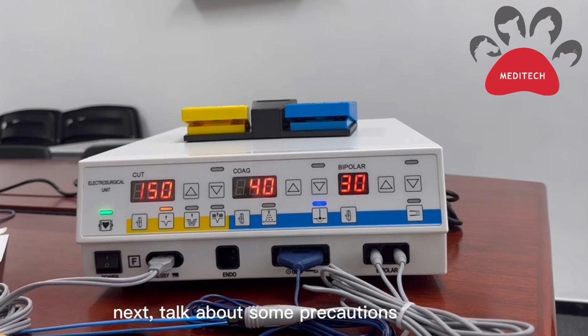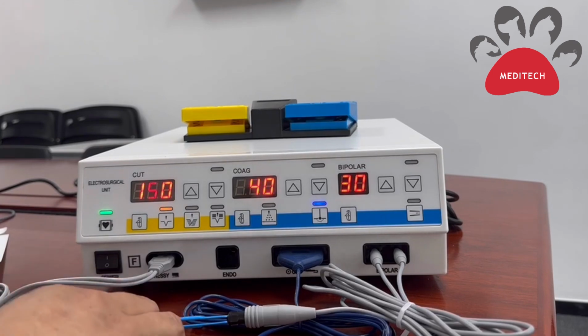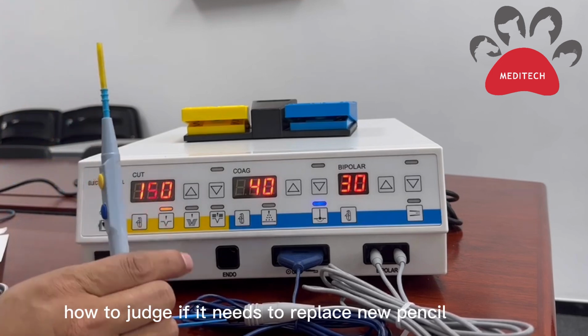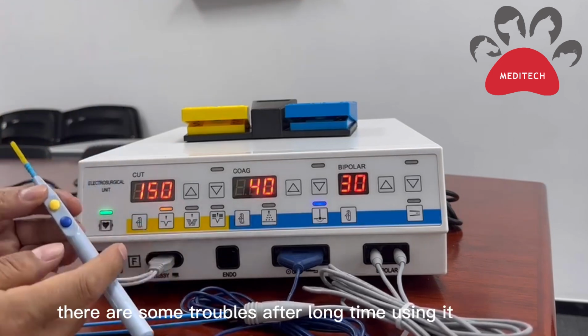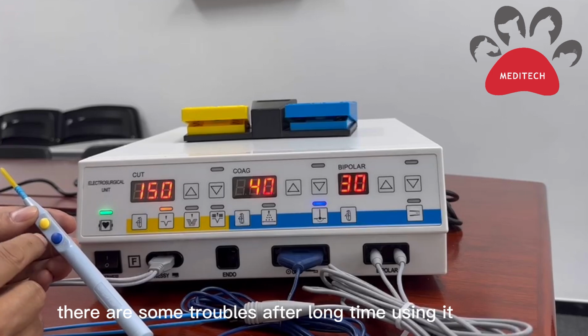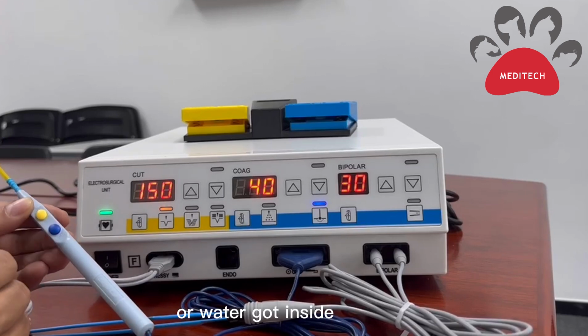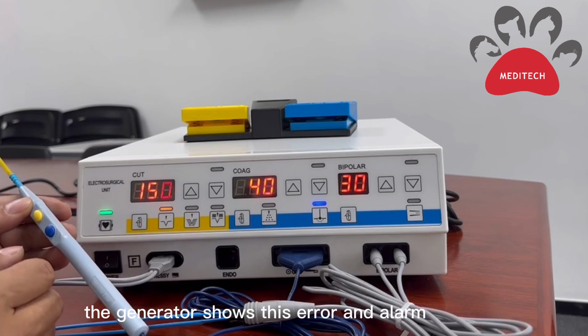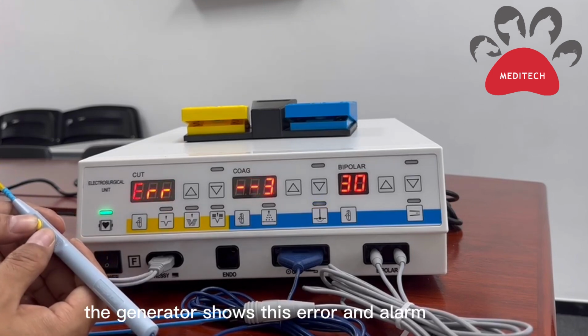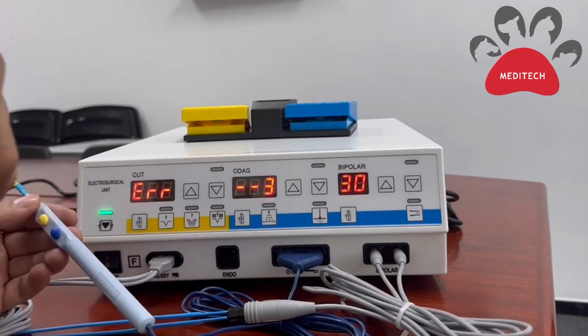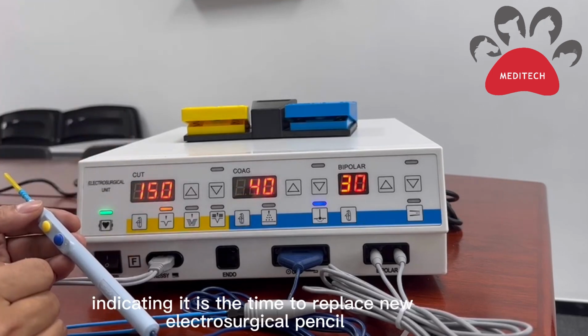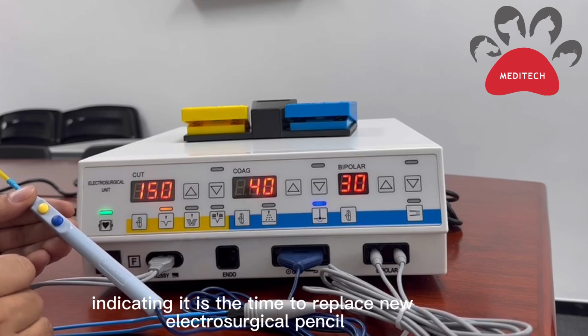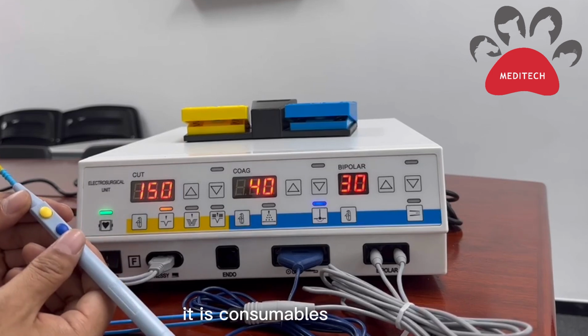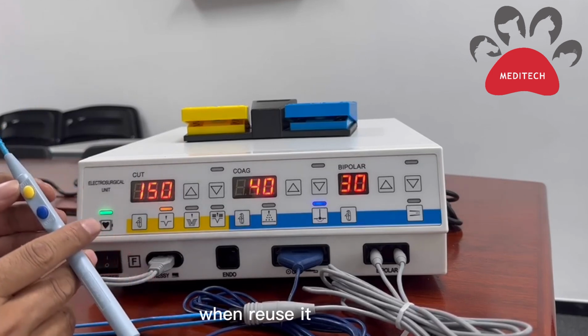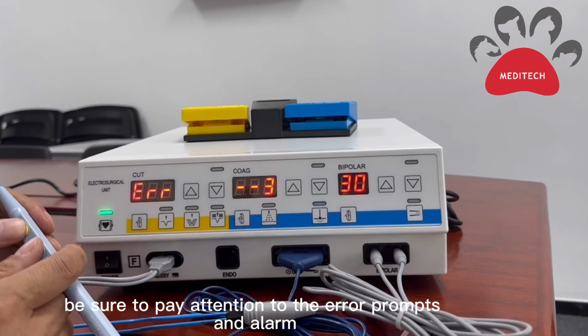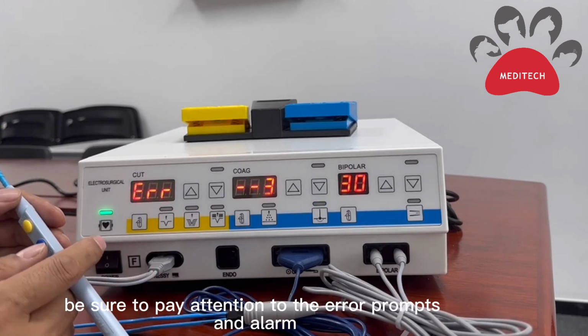Next, let's talk about some precautions. How to judge if it needs a new pencil? There are some troubles after a long time of use, like short circuit or water getting inside. The generator shows this error and alarm, indicating it is time to replace the electrosurgical pencil. It is a consumable. When we use it, be sure to pay attention to the error prompts and alarm.